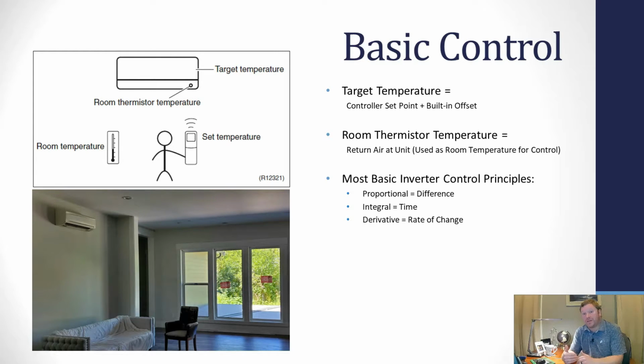And the goal at the end of the day is to get as close to that target temperature as possible without overshooting it. So ideally, if the return air temperature can maintain 73 while the target is 73.5, you're within a half a degree. The compressor ramps as far down as it can, the fans ramp down as far as they can, and then your expansion valve closes down as much as it needs to compensate for that refrigerant flow. And if sized properly, and if installed properly, your system should be able to maintain that target temperature relatively easily.